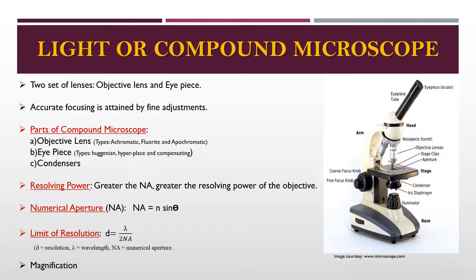The main use of the eyepiece is to magnify the real image of the specimen formed by the objective lenses and to correct defects in the objective. Eyepieces are also called oculars. There are three types of eyepieces: Huygenian, Hyperplane, and compensating eyepieces. Condensers are a series of lenses for illuminating the object on the stage of the microscope by transmitted light. There are two methods: illumination by transmitted light and dark field illumination.